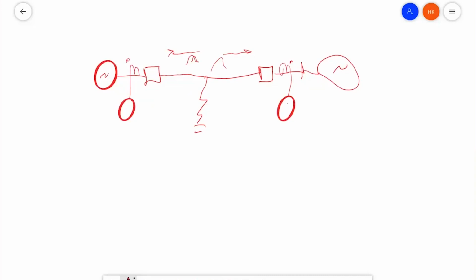And notice I've drawn the traveling waves in this diagram in the positive direction. Now when they reach our CTs, they're going to be entering on non-polarity. So what's going to happen on both of these is we're going to see a traveling wave, but it's going to be in the opposite polarity to that seen on the primary system. And that's because we are entering on non-polarity. So anytime you have an internal fault, the current traveling waves are going to be 180 degrees out of phase on the secondary system versus the primary system. And so this is what it's going to look like for an internal fault. And so that is going to be important.